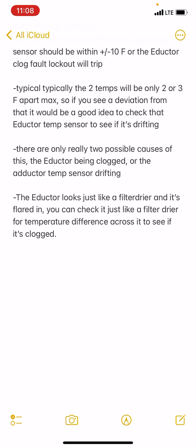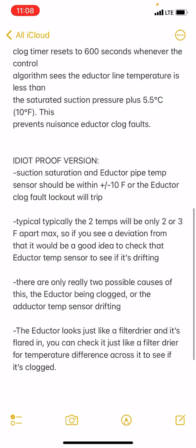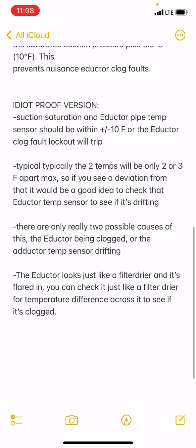The eductor is going to look like a filter dryer — in this case it's black, it's got a pressure port on it, and it's flared in. So you check it just like a filter dryer: look for a temperature difference across it. If there is one, then it's clogged. I go off of three degrees or more — that way you know it's clogged. Anyway, hope this helps somebody.